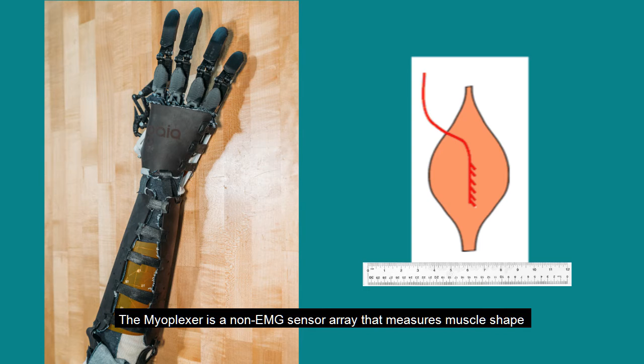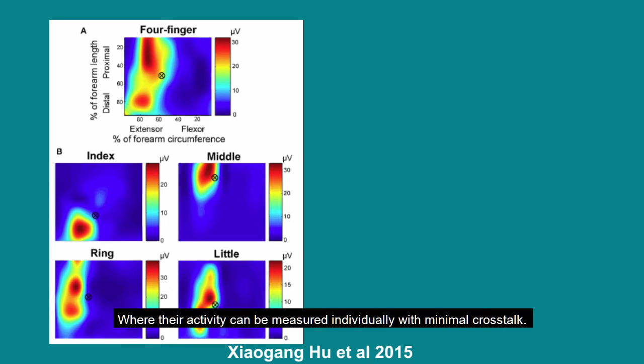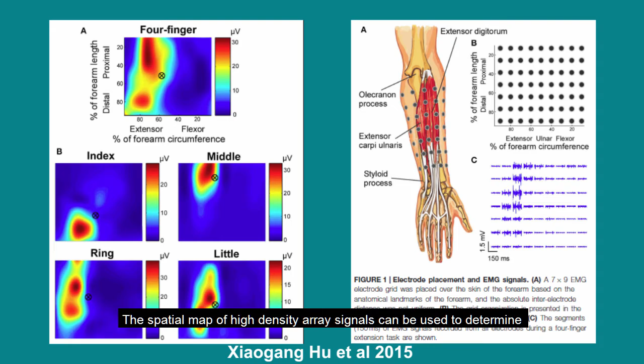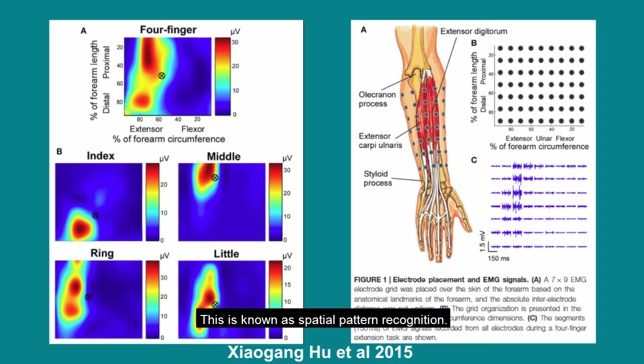The myoplexer is a non-EMG sensor array that measures muscle shape to determine intended finger position in real time. Here's how it works. Finger muscle bellies have unique spatial positions on the forearm where their activity can be measured individually with minimal crosstalk. The spatial map of high-density array signals can be used to determine these indicative spatial positions for every finger from a gesture calibration. This is known as spatial pattern recognition.